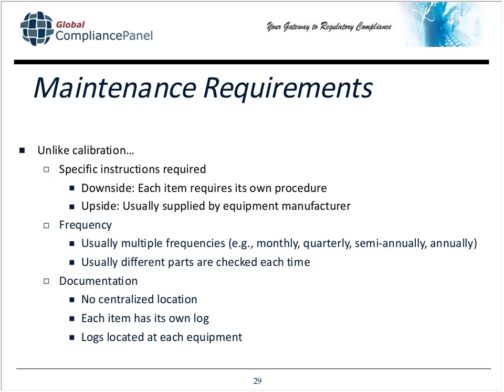When it comes to documentation, unlike calibration, there's really no centralized location because, in practice, each item has its own preventive maintenance log located at each piece of equipment. I know that there are commercially available maintenance programs that preclude this requirement, but more often than not, the people who are using a piece of equipment or the people who are maintaining it want to see the history right there as they're maintaining it. They want to see the processes that they have to maintain at that moment, and then they also want to see the most recent time that they did that.